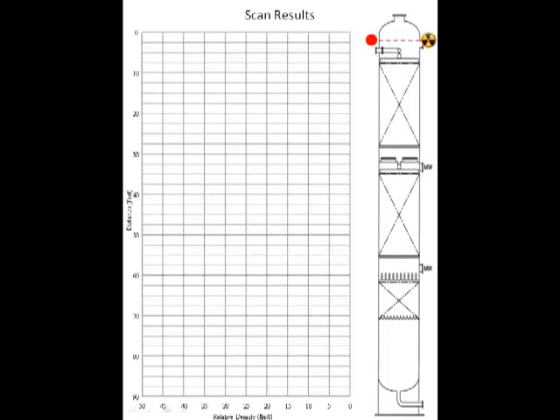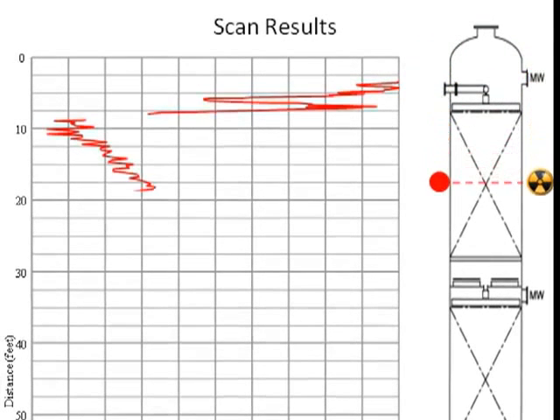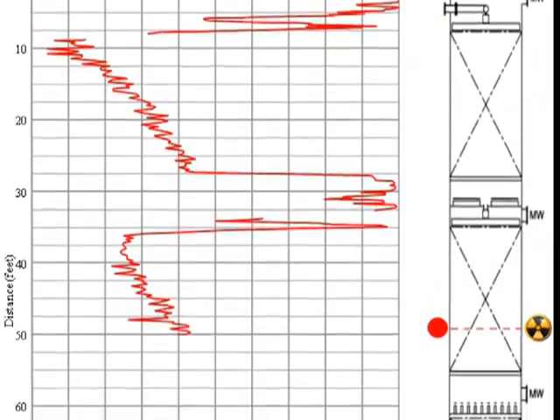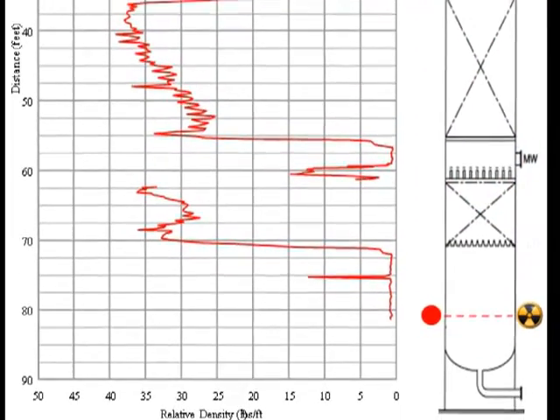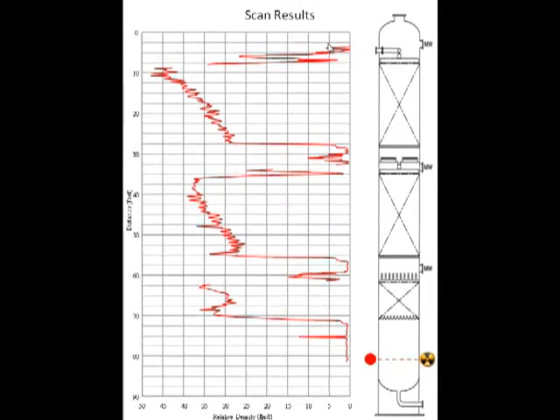The gamma scan started at the top tangent line, and the radioactive source and detector were lowered simultaneously down the tower through each of the three packed beds. This produced a density profile or gamma scan profile that's reproduced on the left.